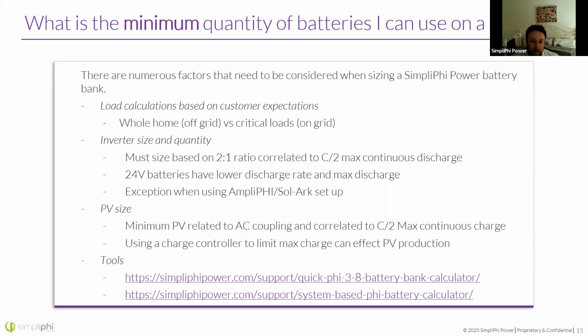Inverter size and quantity is the main thing people mess up on. Let's talk about our standard batteries: they must be sized based on the 2-to-1 ratio, correlating to our C/2 max continuous discharge. Meaning, if we have a 3.8 kilowatt hour battery, we can only discharge 1.9 kilowatts continuous from that battery, so your inverter must reflect that. If you have one 3.8, the maximum inverter size is a 1.9 kilowatt inverter, so you'd never over-discharge the battery. This gets messed up a lot—I see a lot of 8,000 watt inverters paired with two of our batteries. Again, it's the max discharge of the battery bank, so that 1.9 does add up.